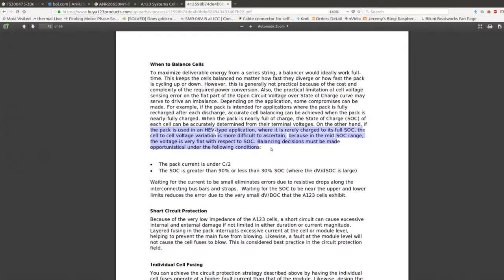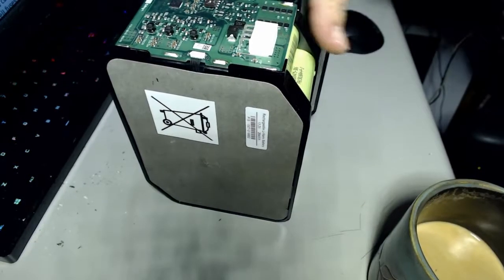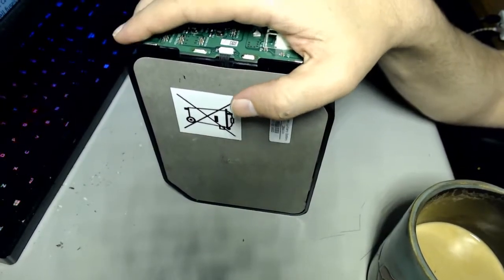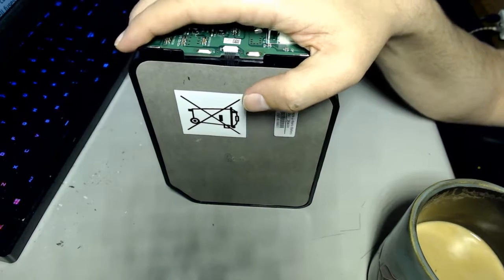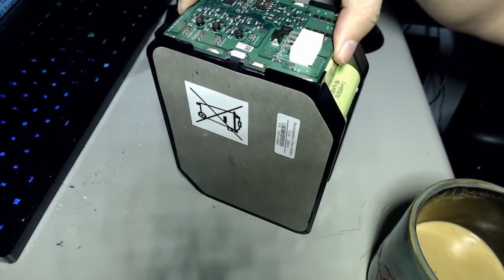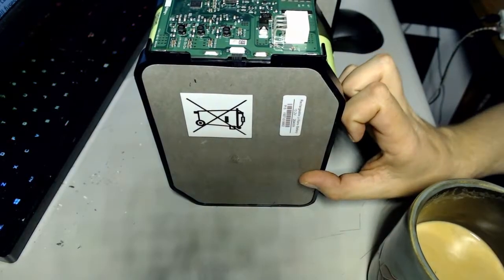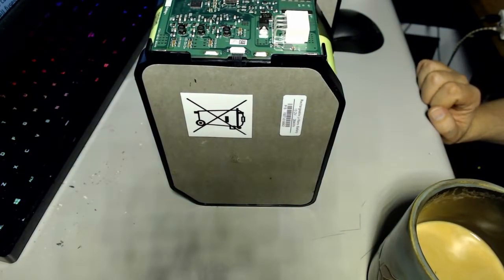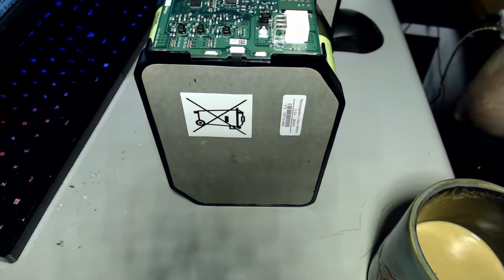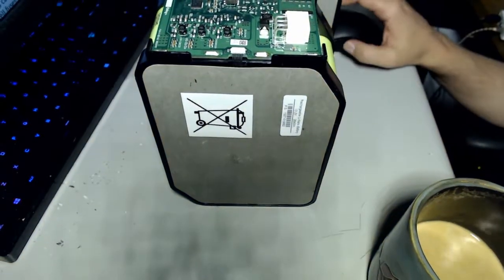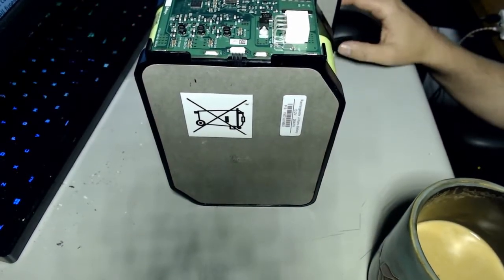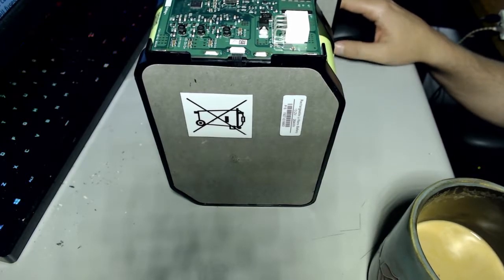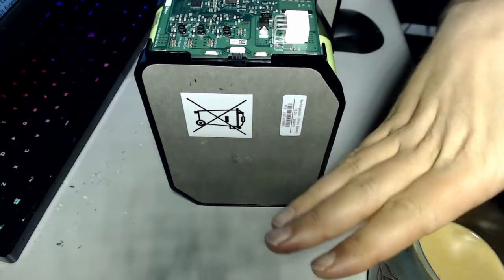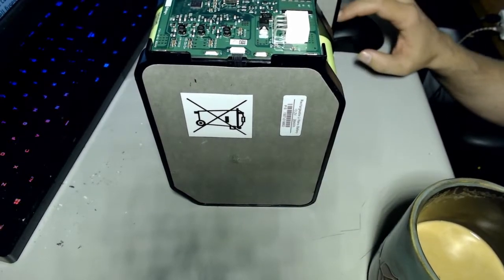But right now these cells, which aren't lithium ion, being that they're each at 2.7 volts, I know it's safe to pull voltage, and I know I could charge this even without a balance pack on here. Monitoring each string isn't necessary to a degree, as long as you're not pushing the upper and lower limits all the time, and not pulling currents that could sag voltage down beyond where it's supposed to be.